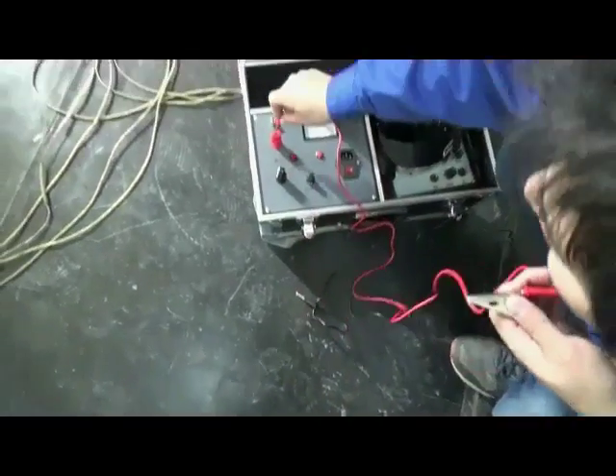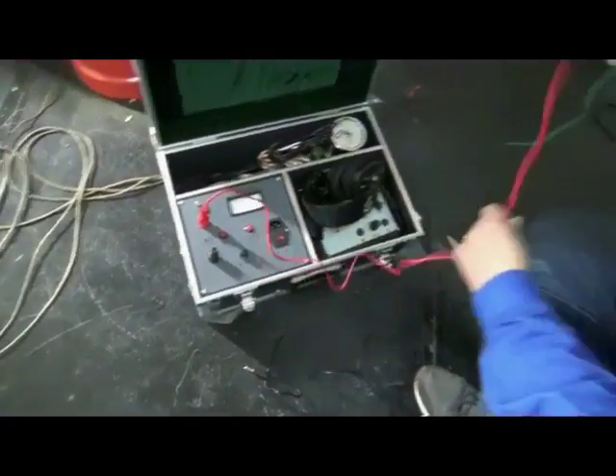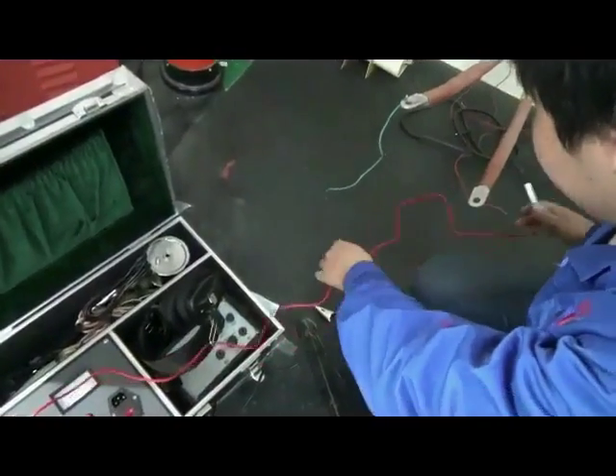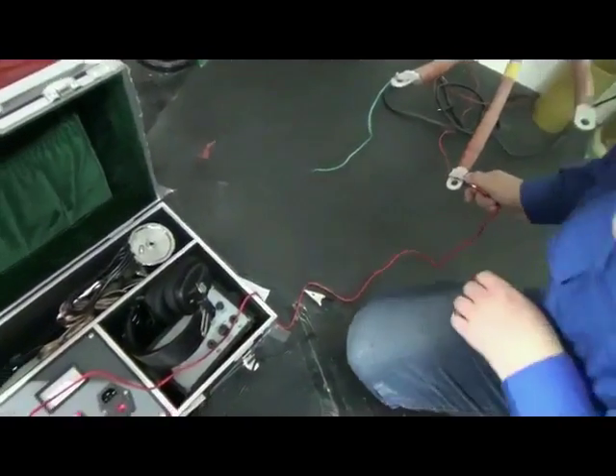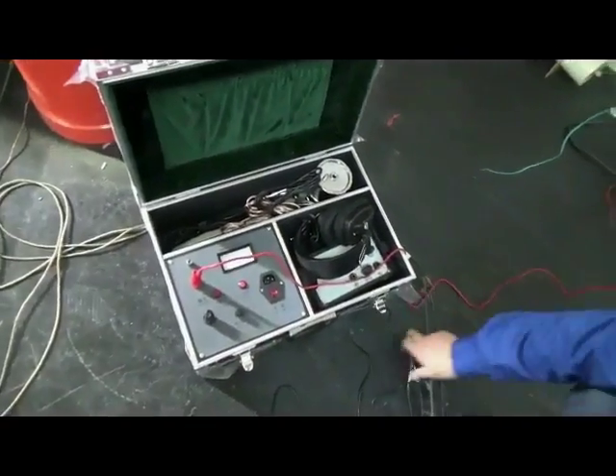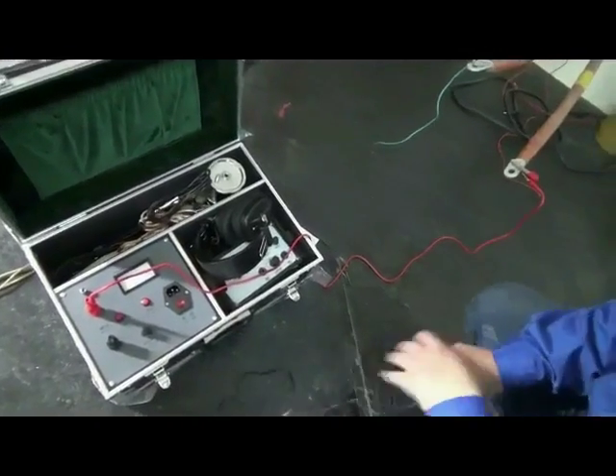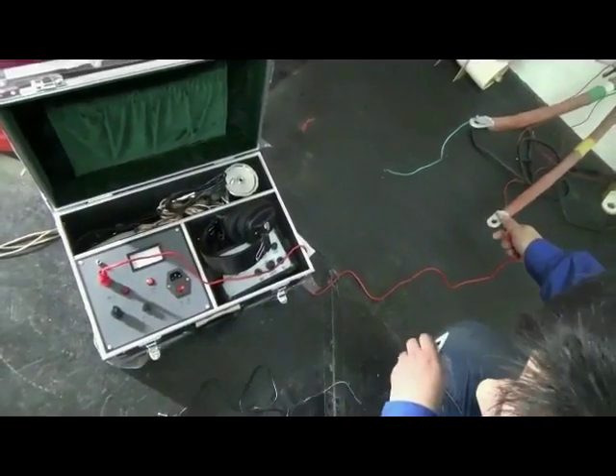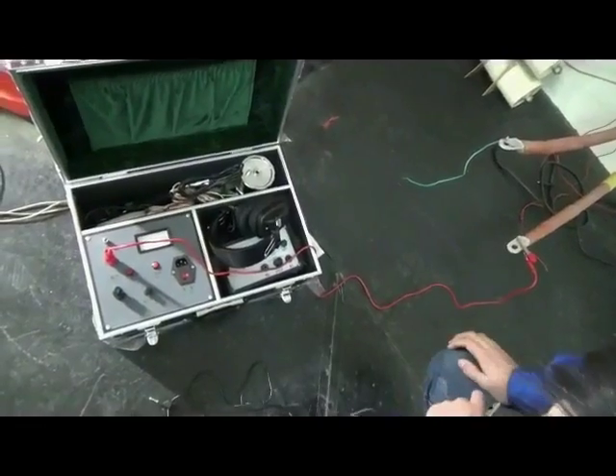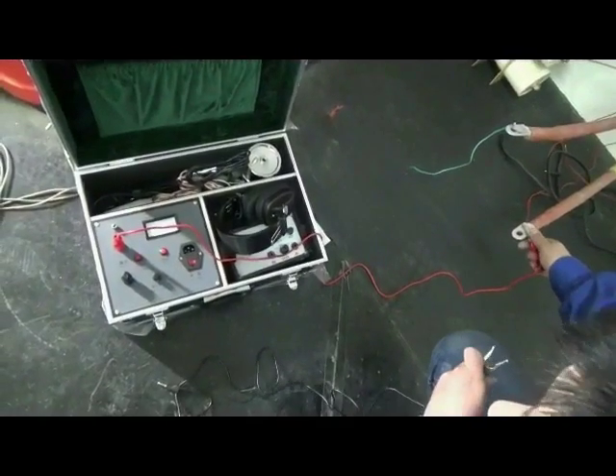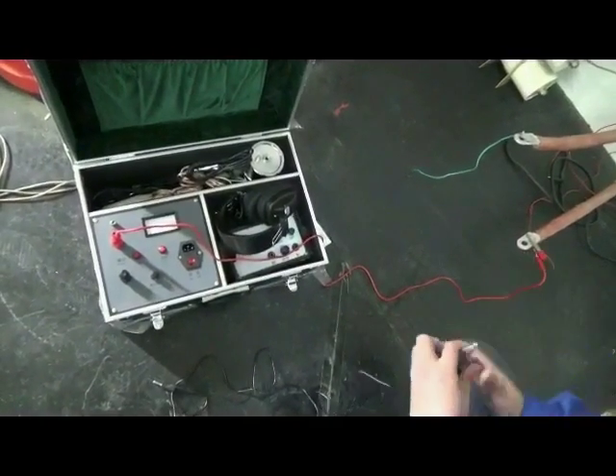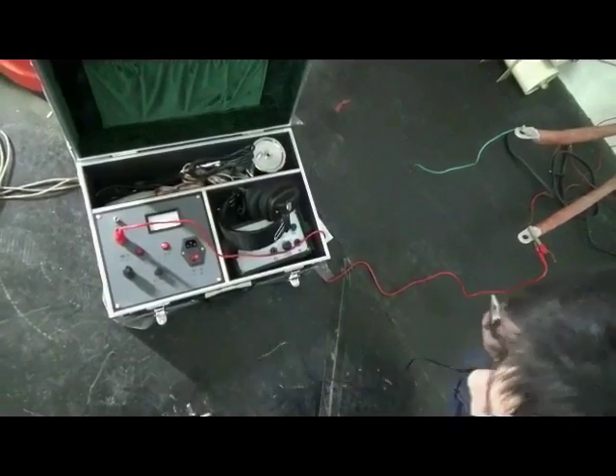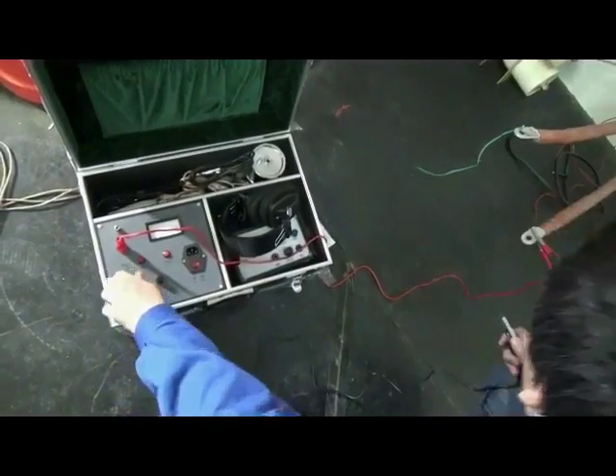The red will be connected to red terminal and the other end connected to phase cable. Normally, the best practice is to connect this line to a good phase cable. In case of faulted cable, the best practice is to connect to the phase cable with the highest resistance value.